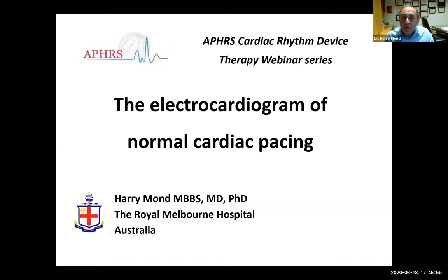I'd like to start with polarity, and there are two ways to pace the heart muscle, unipolar and bipolar. For unipolar, there is a single pole on the lead, which is the cathode, and the anode lies on the pulse generator can. Whereas with bipolar, we have both anode and cathode on the lead, and hence the term bipolar.